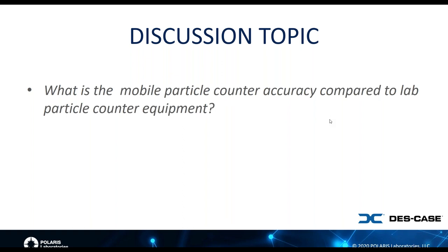Yeah, that is actually one of the benefits of having a portable particle counter. If you set it up properly, put the sample port in the right place, as you said, Bob, and probe onto that sample port in the right location, you eliminate the potential of getting erroneous particles in the sample, either through poor bottle cleanliness, poor handling of the sample, or something in transit. So there are benefits to having portable particle counters in the field, but I don't think anybody would suggest that it displaces the lab.